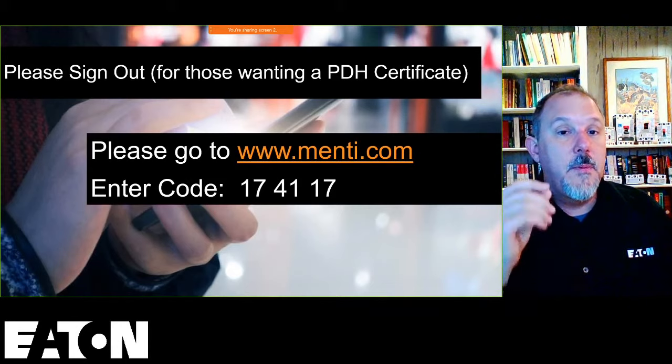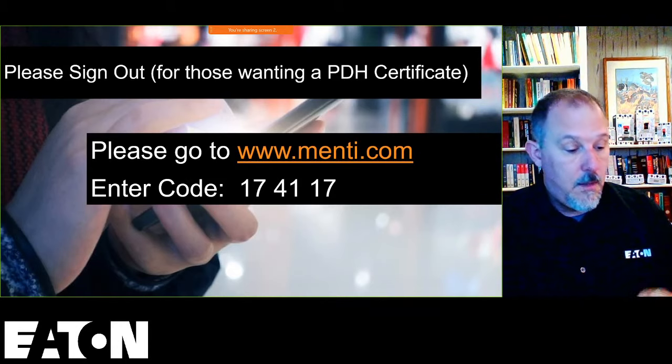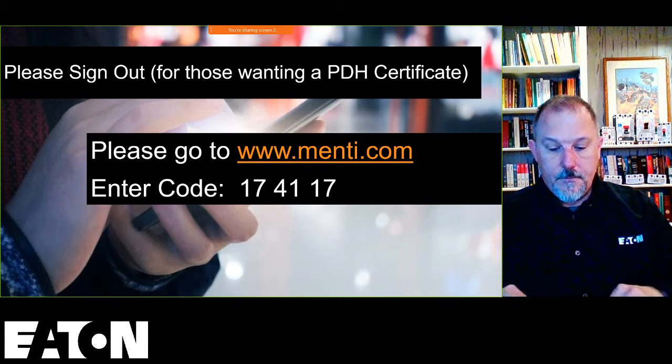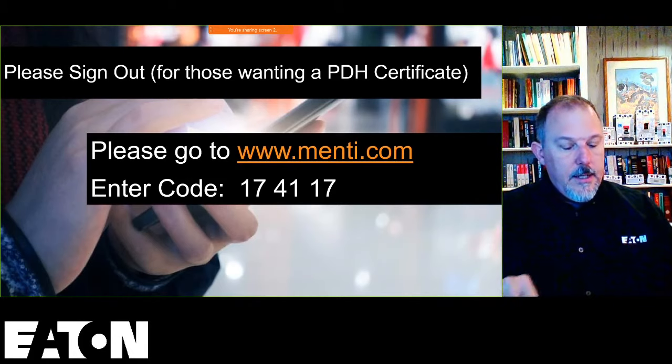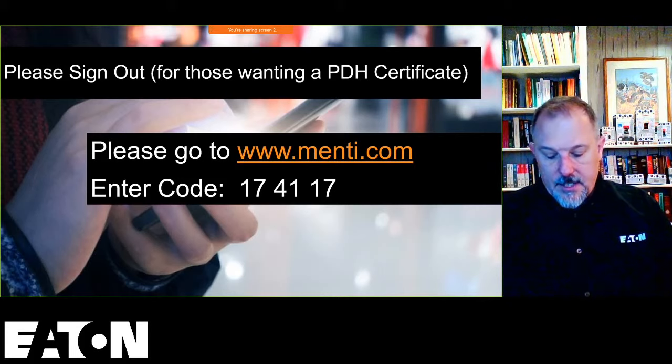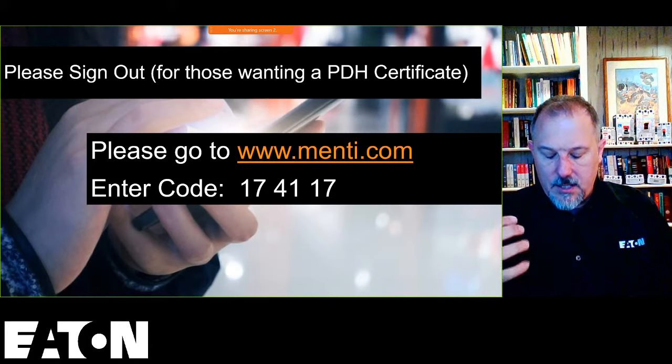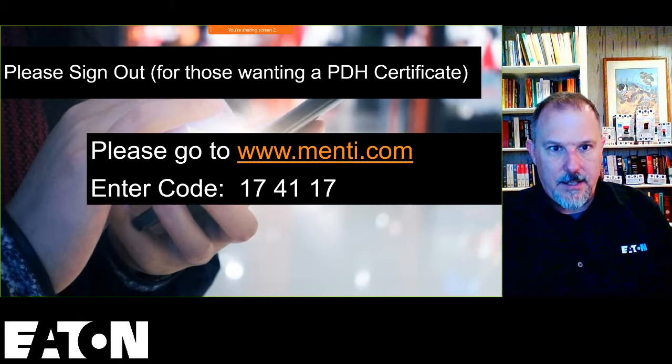Now, what about the maximum overcurrent protection device? The maximum overcurrent protection device is already calculated on the nameplate, as required by B, which requires compliance with part four. Part three, rather. Yeah. And that's the reference I had too, but for some reason in my mind, that's a lot more clear than the minimum circuit ampacity.